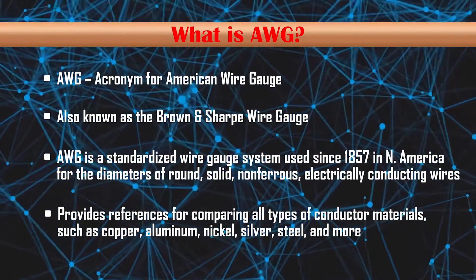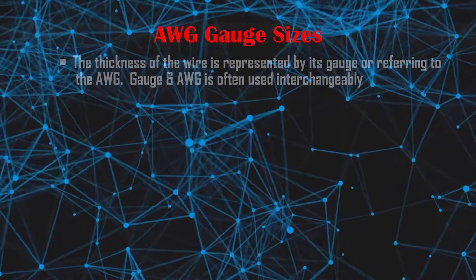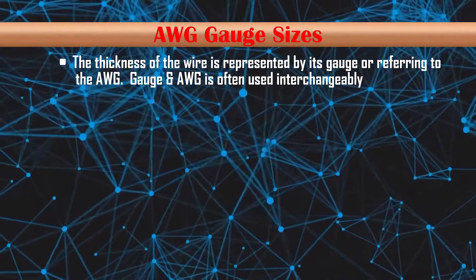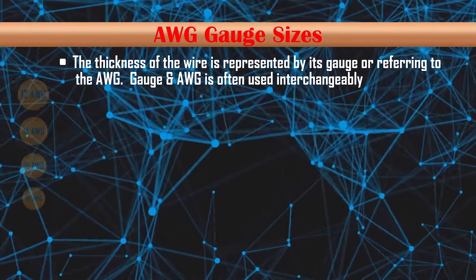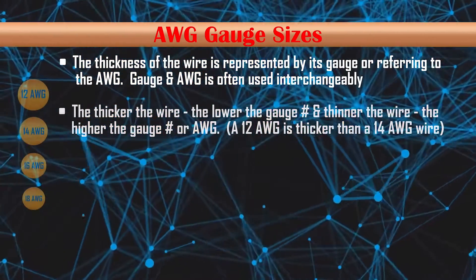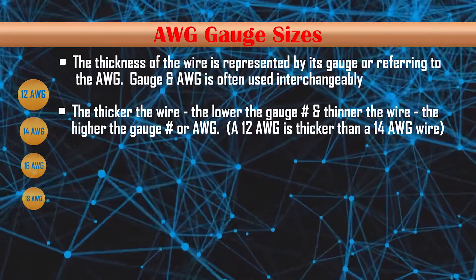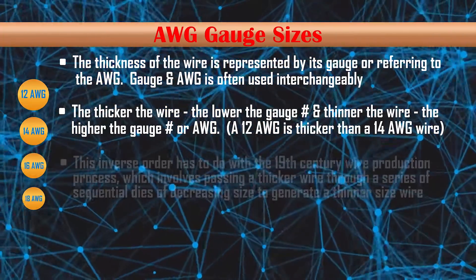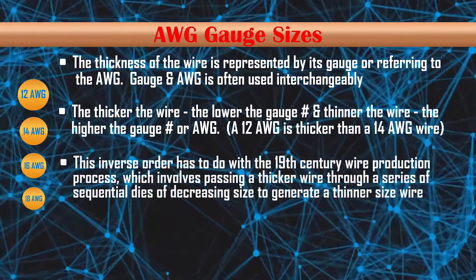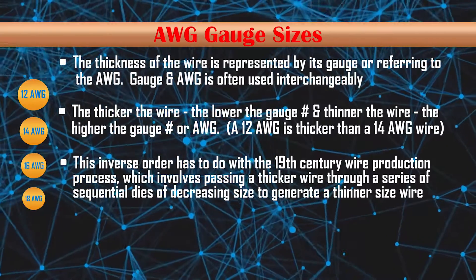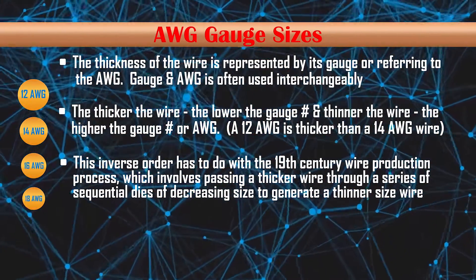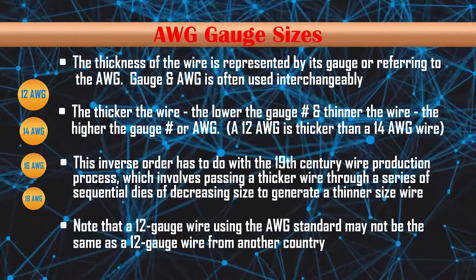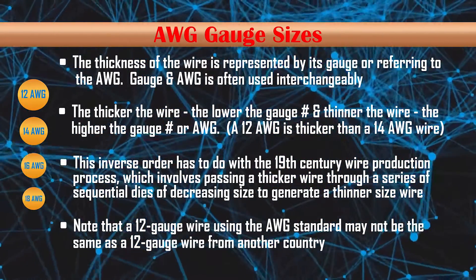AWG gauge sizes represent the thickness of the wire. The thicker the wire, the lower the gauge number, and the thinner the wire, the higher the gauge number. For example, a 12 AWG is thicker than a 14 AWG wire. This inverse order relates to the 19th century wire production process, which involves passing a thicker wire through a series of sequential dies of decreasing size to generate a thinner wire. Note that a 12 gauge wire using the AWG standard may not be the same as a 12 gauge wire from another country.